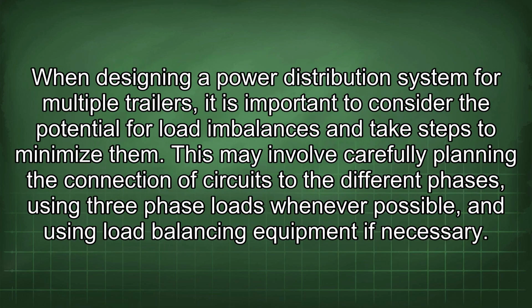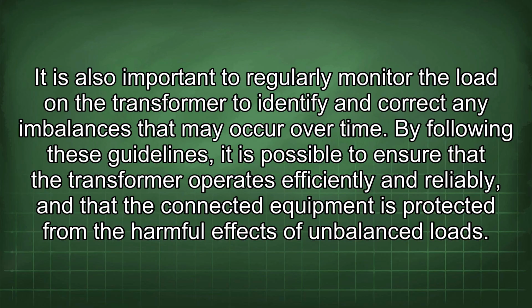When designing a power distribution system for multiple trailers, it is important to consider the potential for load imbalances and take steps to minimize them. This may involve carefully planning the connection of circuits to the different phases, using 3-phase loads whenever possible, and using load balancing equipment if necessary. It is also important to regularly monitor the load on the transformer to identify and correct any imbalances that may occur over time. By following these guidelines, it is possible to ensure that the transformer operates efficiently and reliably, and that the connected equipment is protected from the harmful effects of unbalanced loads.